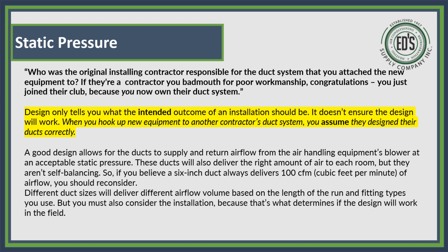Who was the original installing contractor responsible for the duct system that you attach your new equipment to? If they're a contractor that you've badmouthed for poor workmanship, well, congratulations. You just joined their club because now you own their duct system. Design only tells you what the intended outcome of an installation should have been. It doesn't ensure the design will work. When you hook up new equipment to another contractor's duct system, you assume that they designed their ducts correctly.